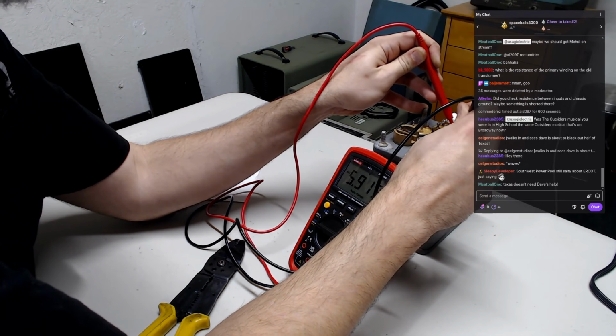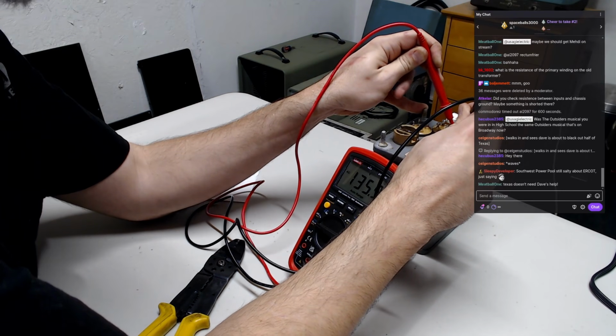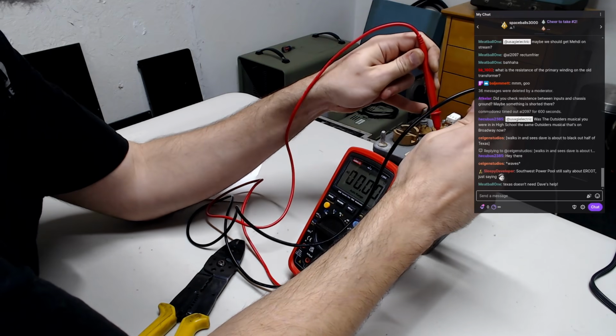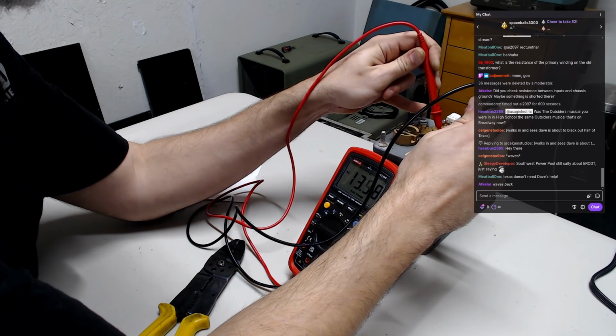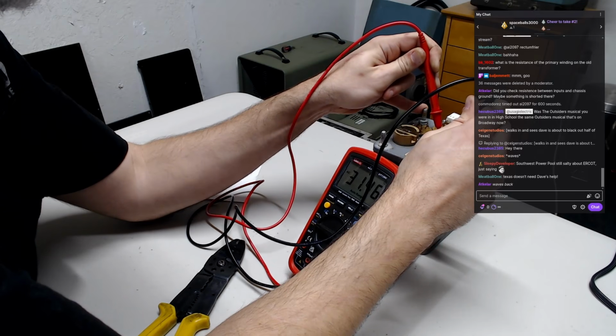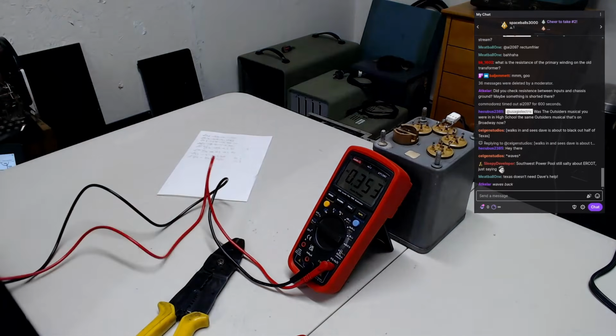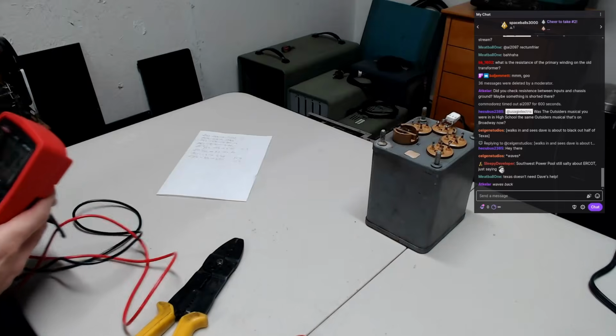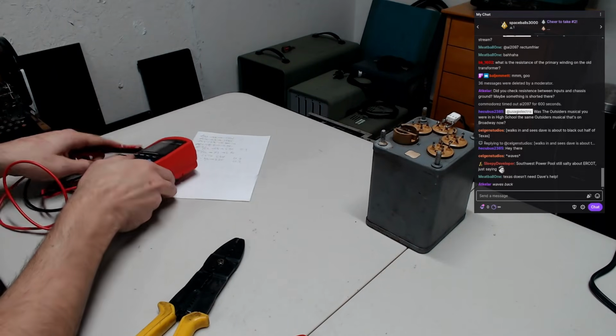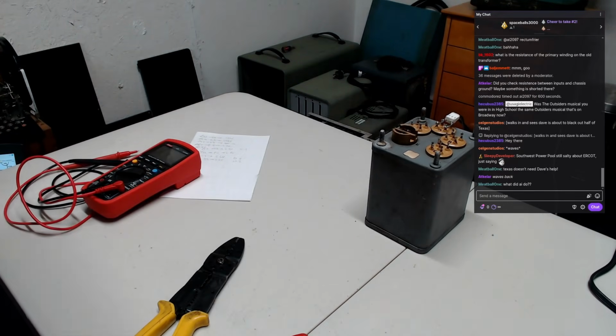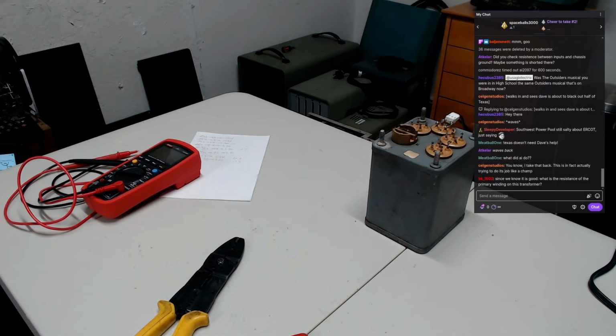And then B1 to B2 should be our 100 and some odd. Come on. There it is, 136 on B1 to B2. And 30 volts was C1 to C2, right? Which is what we had. Yeah, that transformer is totally fine. We didn't need to replace the transformer at all. Okay. Well, that sucks, but also means I have a spare transformer.